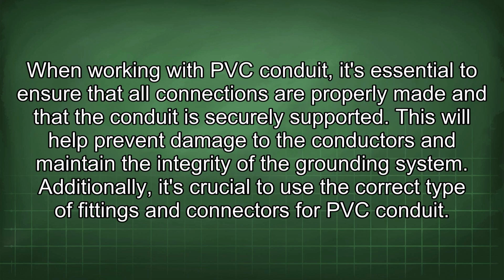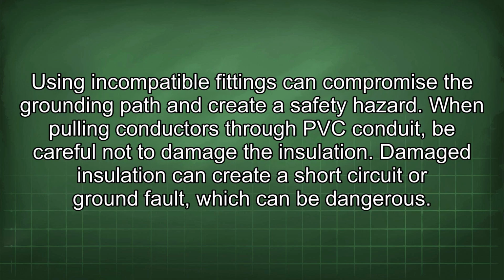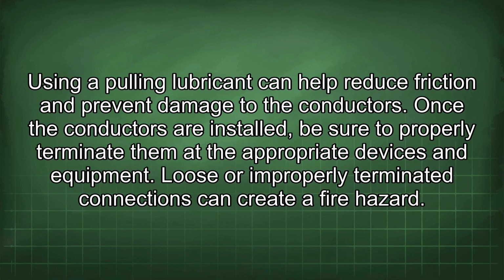When working with PVC conduit, it's essential to ensure that all connections are properly made and that the conduit is securely supported. This will help prevent damage to the conductors and maintain the integrity of the grounding system. Additionally, it's crucial to use the correct type of fittings and connectors for PVC conduit. Using incompatible fittings can compromise the grounding path and create a safety hazard. When pulling conductors through PVC conduit, be careful not to damage the insulation. Damaged insulation can create a short circuit or ground fault, which can be dangerous. Using a pulling lubricant can help reduce friction and prevent damage to the conductors.